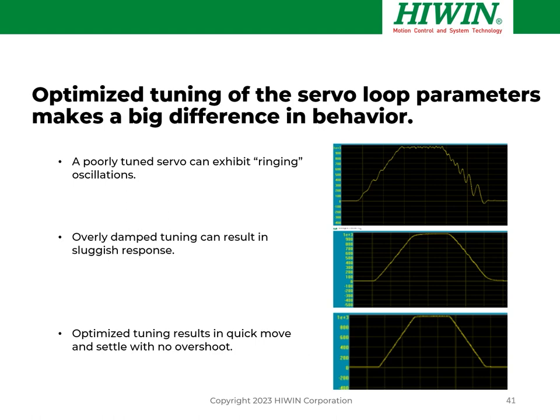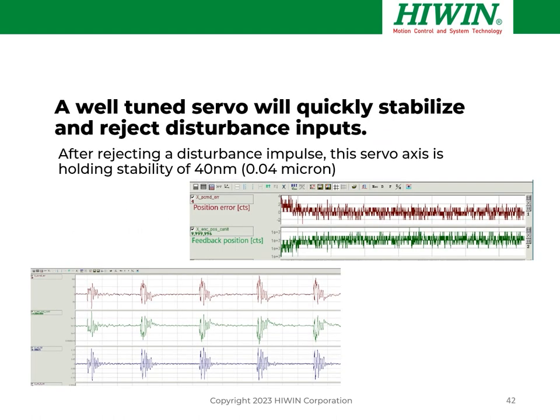Optimized tuning can make a big difference in behavior. Three pictures of servo loop performance to a trapezoidal profile illustrate this: if poorly tuned, you get ringing and oscillations — the system never calms down, wasting energy and generating heat. An overly damped system results in sluggish performance — you can have a very high-performance linear motor but if it's detuned, you don't realize its capability. With optimized tuning, you get quick move-and-settle with no overshoot; you can also optimize for scanning with low ripple using notch filters to remove unwanted frequency disturbances so the servo doesn't excite those resonances. A well-tuned servo quickly stabilizes and rejects disturbance inputs. One real system example showed it holding stability of 40 nanometers (0.04 microns) — outstanding performance from a well-designed, properly specified, and optimally tuned system.